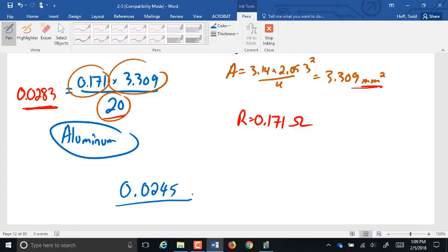But it was actually very common. In fact, there's a house on 48 here over by Cumberland that I inspected that they actually had done this. They had actually clipped off the aluminum wires, spliced copper. So there was copper going into the box and hid the splice into the floors, which is doubly wrong because you've got the aluminum wires in the walls, but now you've got a spliced wire shoved into the wall as well, which is really bad.